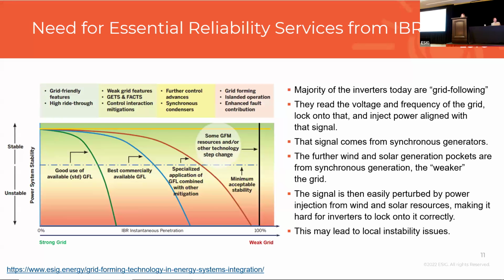This signal comes from synchronous generation. So the further wind, solar, and batteries are from synchronous generators, the weaker the grid. When you hear weak grid conditions, that means this part of the grid is far away from a strong synchronous generator source, and this weaker signal is easily perturbed by injection of megawatts from wind and solar itself.